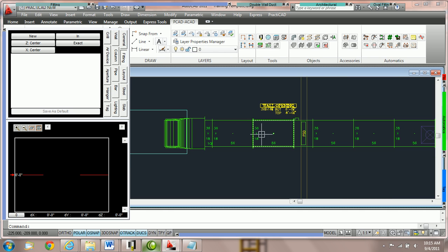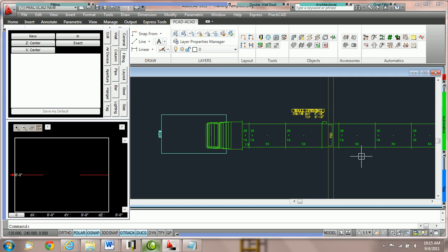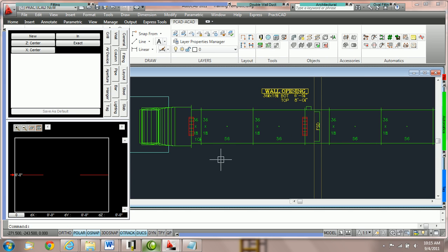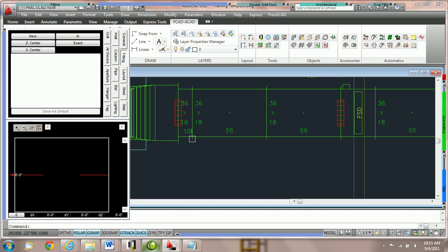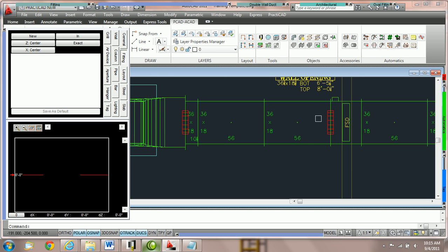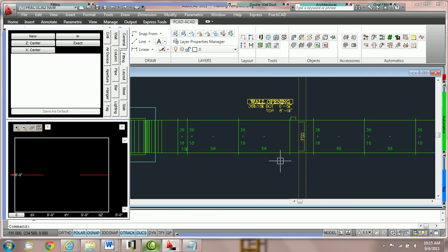As a matter of fact, there is an option in the software called duct line checking, which allows us to highlight our duct line and then run automatics, which will actually flag the points that duct is not connected. Notice that right here and right here, PractiCAD has stated that duct isn't connected, and that's because we did not connect it correctly.